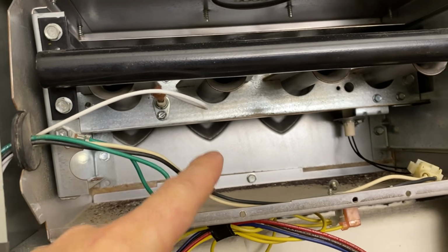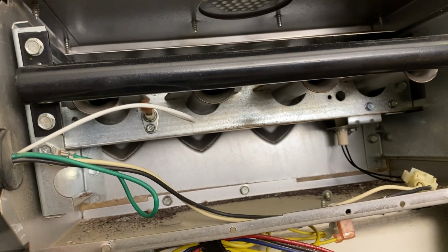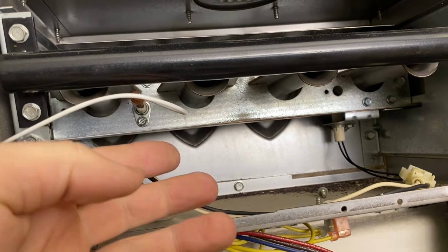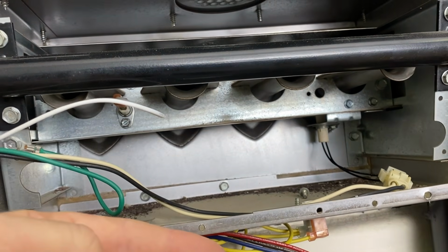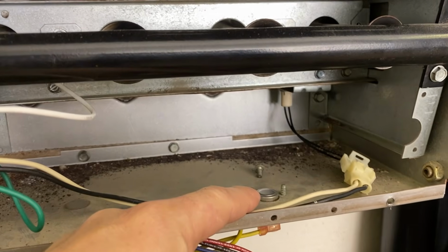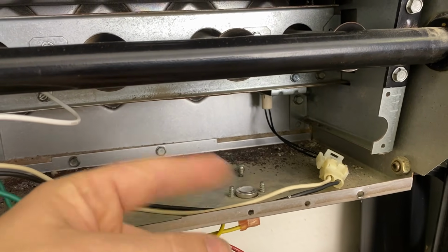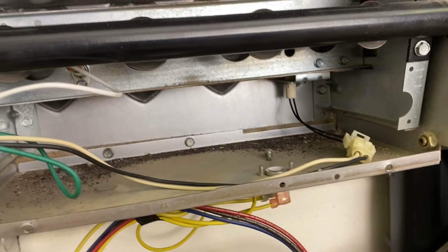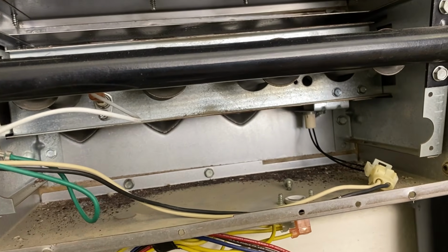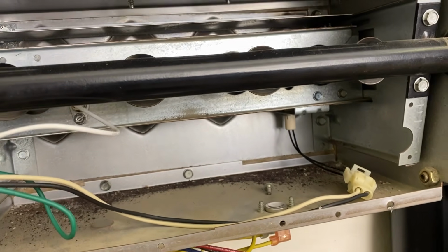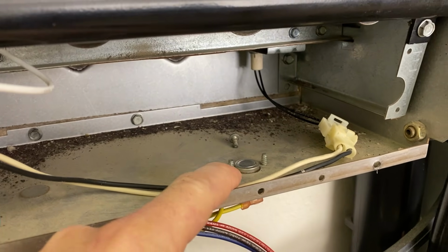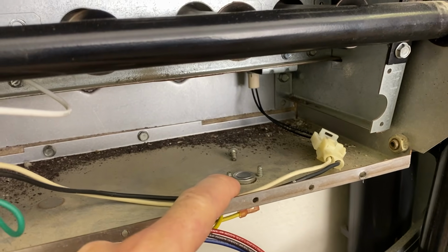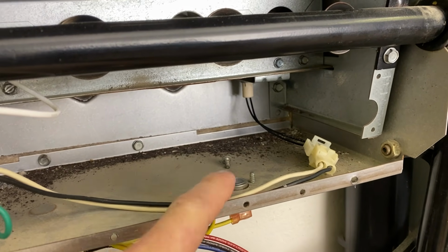Another thing that can happen is if you get a clog somewhere in your heat exchanger or in the vent or something like that, you can get what's called rollout, which means flames roll out into here. And there's also a sensor here for that. If this senses flames rolling out in here, it'll shut everything off also. And then you've got another problem. You've got something clogged or something like that going on. Sometimes this sensor could also go bad, and that would be a trouble code that you would get, and that would tell you what the problem is there.